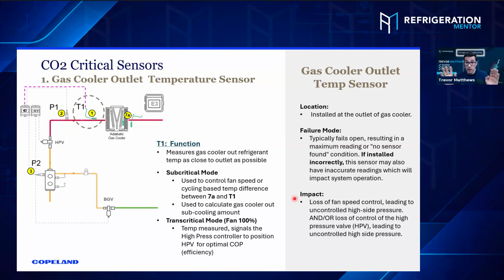Will it work? It will run. Don't get me wrong, it will run. But when you start to run into issues, that is probably the problem. You know what I mean? So you've got to follow the manufacturer's recommendation at the outlet of the gas cooler, as close as possible. That's right. It's okay for the pressure transducer to be in the building because pressure losses are insignificant for the few feet, but temperature is very different.